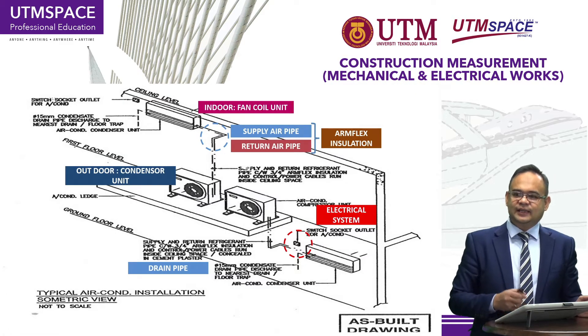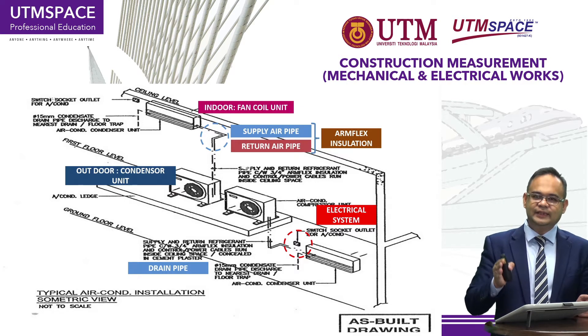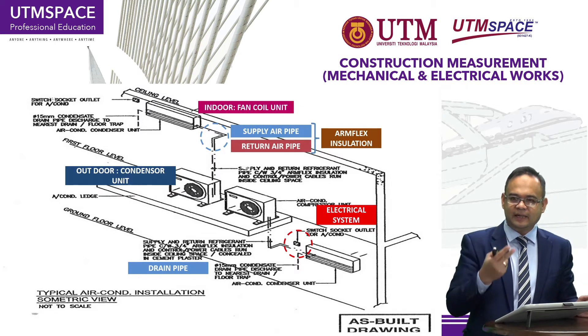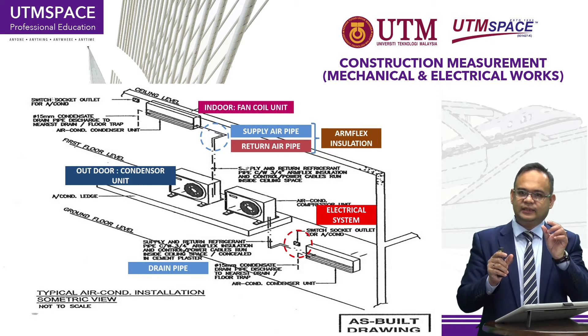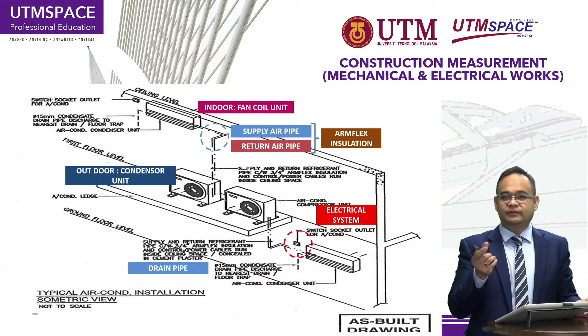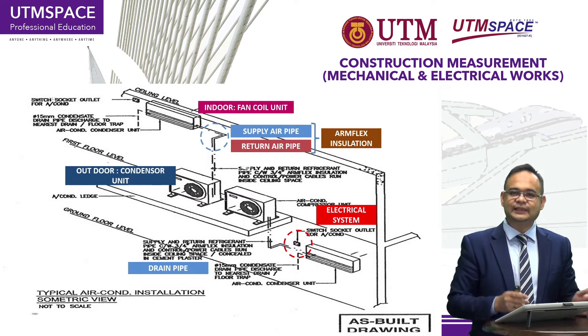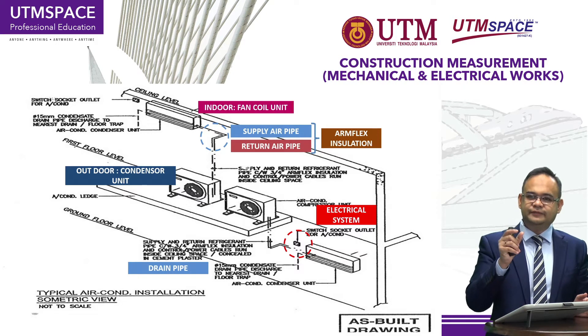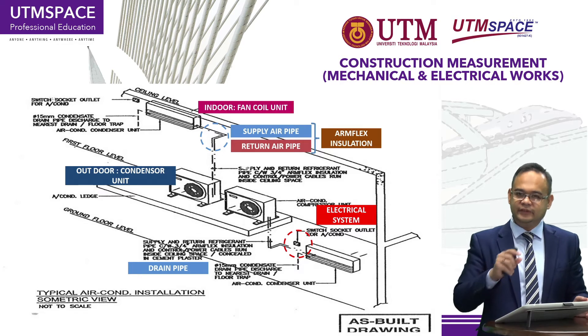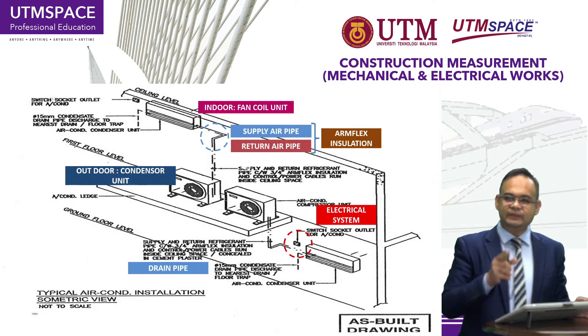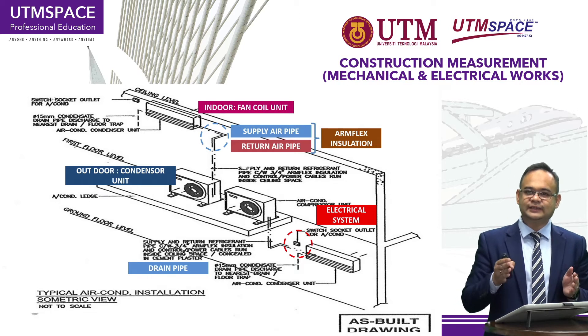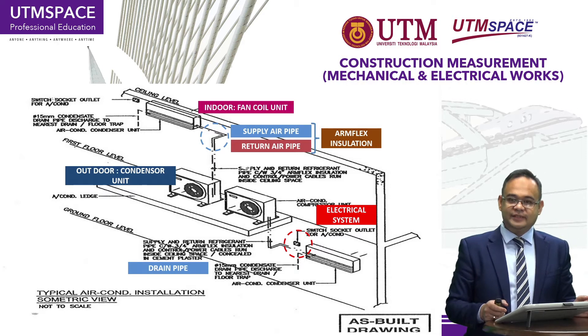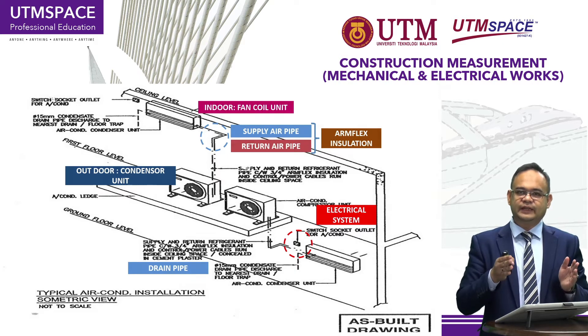This is the detailed schematic showing the connection between the outdoor unit and the indoor unit. We have two types of pipes: the supply pipe and the return pipe. The diameter of the supply pipe is smaller compared to the return pipe — for example, 13 mm diameter for the supply and maybe 25 to 26 mm diameter for the return pipe, depending on the manufacturer's technical specification. Insulation is very important for the supply pipe to control the temperature of the gas being supplied to the FCU.